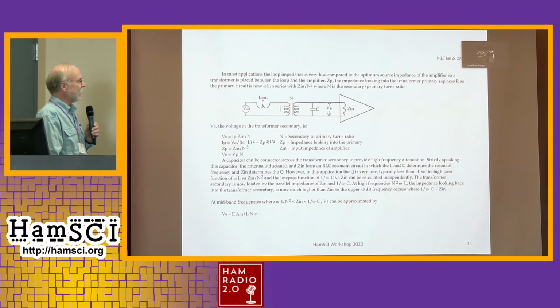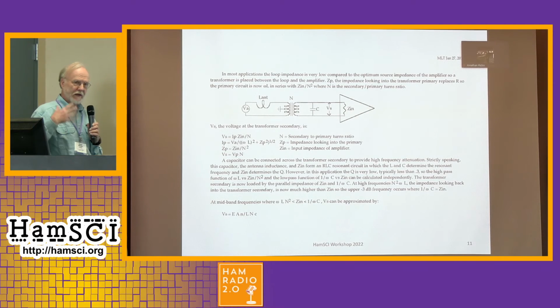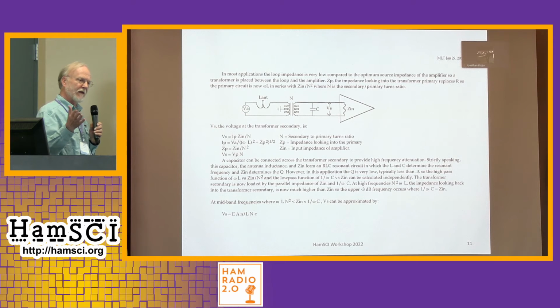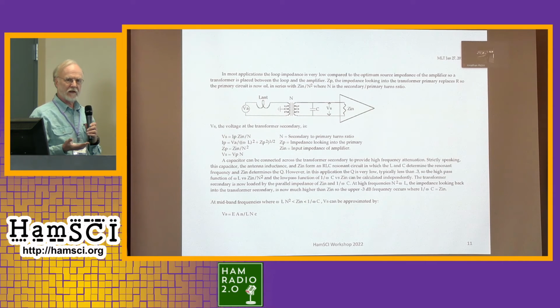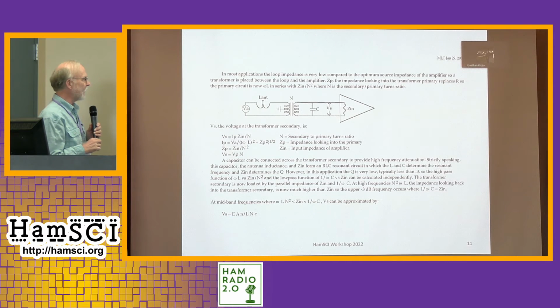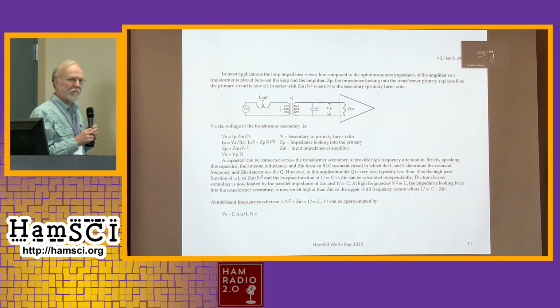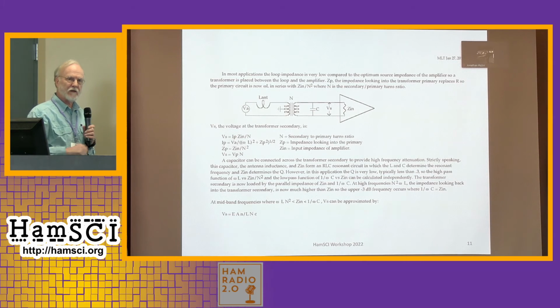You have the inductance of the antenna. It's working into a load resistance, and over a broad range of frequency, the induced signal follows the increased impedance of the inductance. So it actually ends up giving you a very constant signal over a wide range. And then the inductance at the low end has it roll off, and then the capacitance that you see as the input impedance, part of the input impedance of the amplifier, gives you a high frequency roll off. And this is showing that in our amplifiers, we usually use a transformer because the input impedance is usually up in the kilo range, but the antenna is more down in the tens of ohms range. So you want to match that to maximize your signal sensitivity.